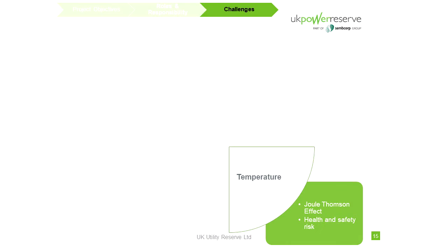So encountering a high pressure gas connection was the first time, and it came with unique challenges, which I'm going to be talking us through today. The first encounter was temperature. Very unique. I'd never had an issue with the temperature of the gas when they dropped the pressure from 7 bar. It's never been an issue.